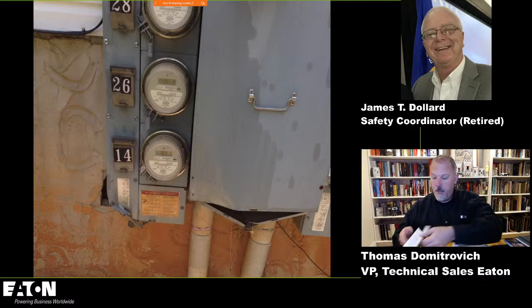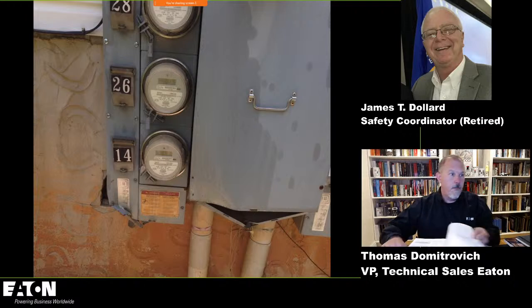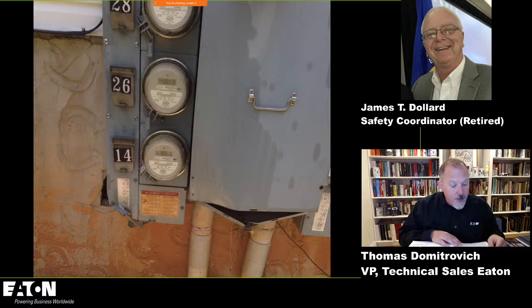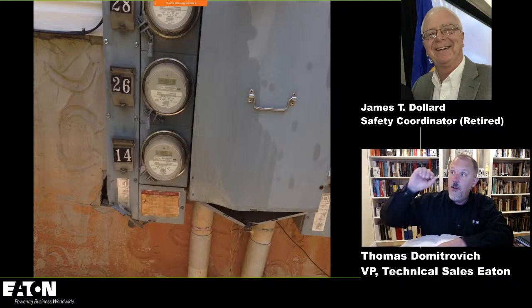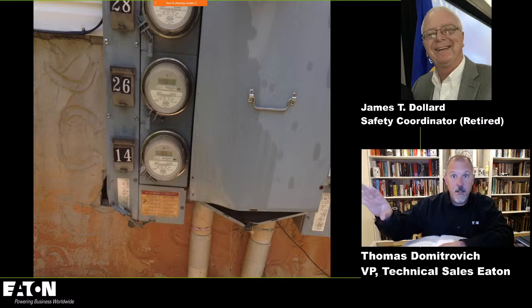Now, the picture that you have here is a really good example. You take a look at a piece of equipment like this, there's nothing normal about it. So there could be no action with respect to NFPA 70E 130.2(A)(4) that would be considered normal, because this equipment is in really, really bad shape. And you brought up a good point in Table 130.5(C), the estimate of the likelihood of occurrence, because we talked about that at the very beginning. When you look at the tasks, like reading a panel meter or performing infrared thermography, the second column says equipment condition, and it usually says any, normal, or abnormal. So anything you do on this equipment, because of its condition of maintenance, would be abnormal.